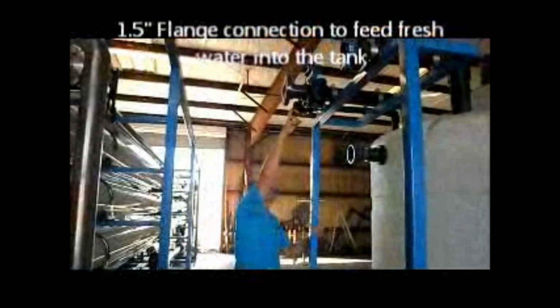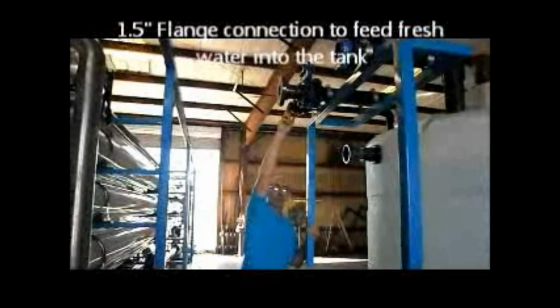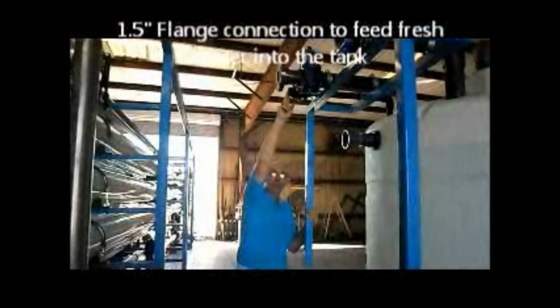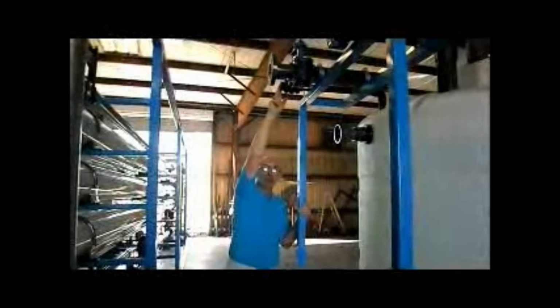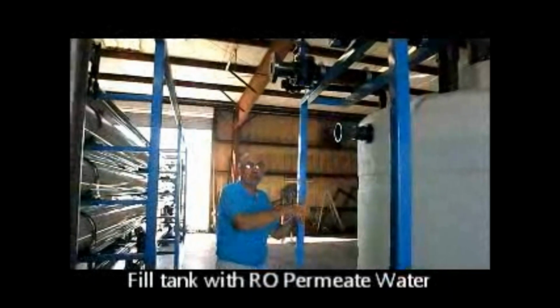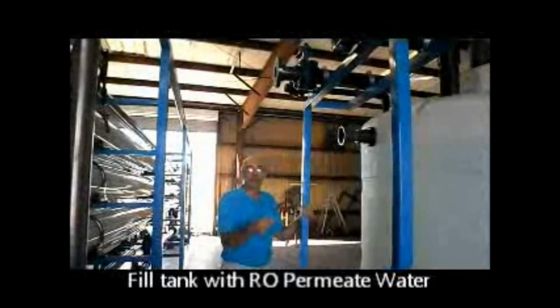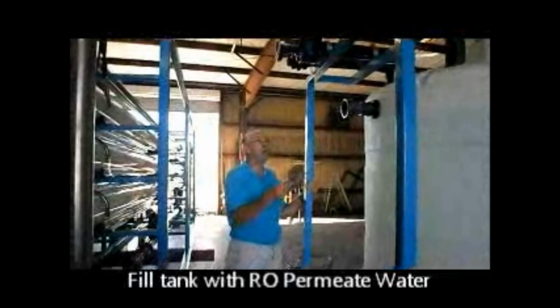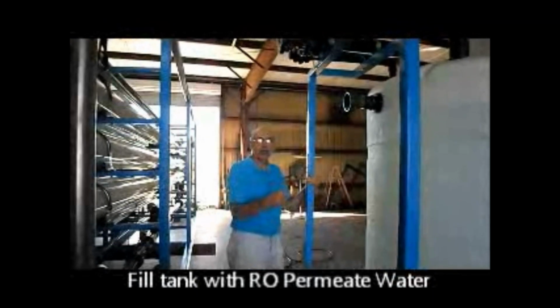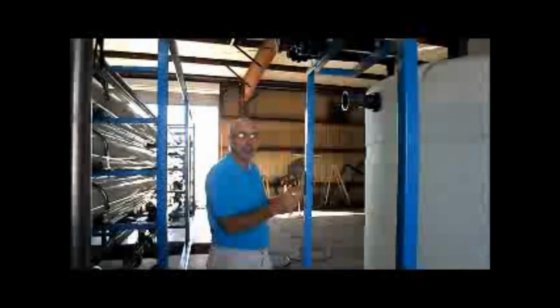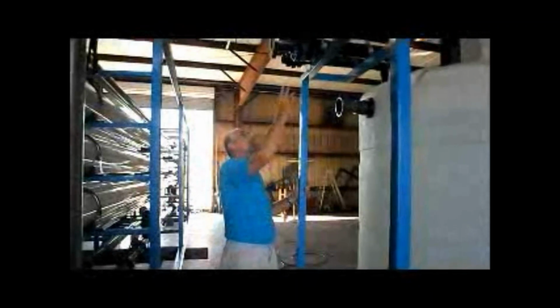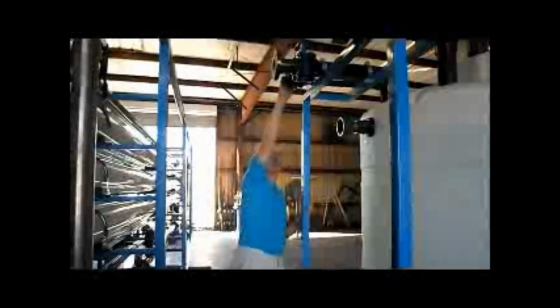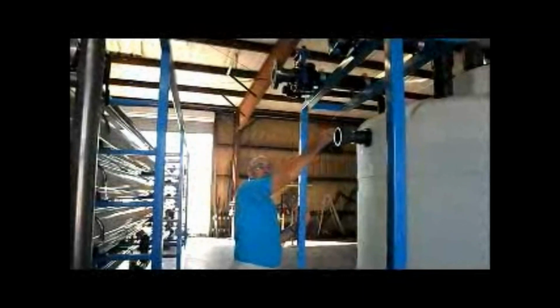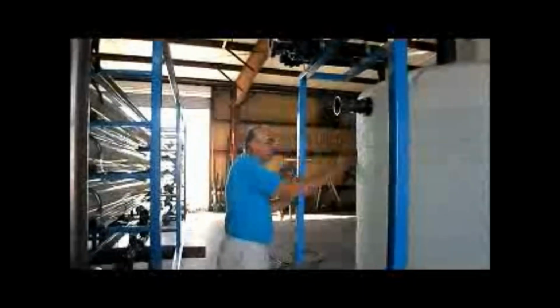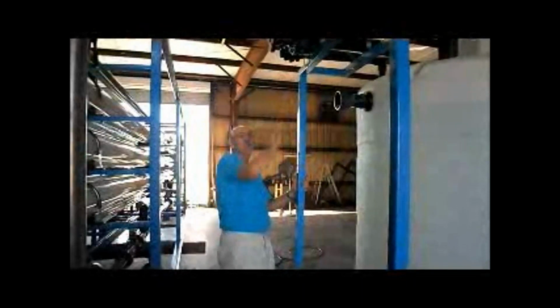The first one, right here, is a 1.5 inch pipe connection. This is for bringing fresh water into the tank. If you're going to mix out chemicals, you should always start first with some RO permeate water. Fill this up before adding the chemical. Always add the chemical to the water, not the water to the chemical. So you open this valve and you can bring pressurized feed of RO permeate water into this tank to fill it up. This is strictly a fill valve.